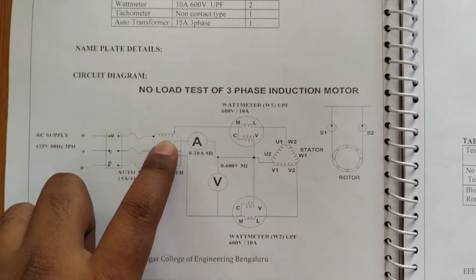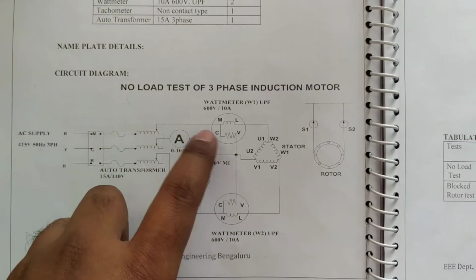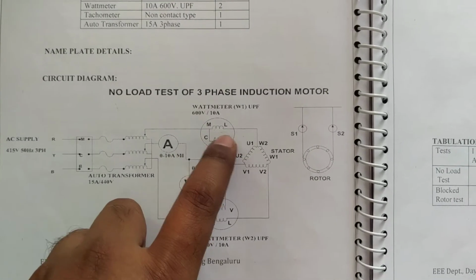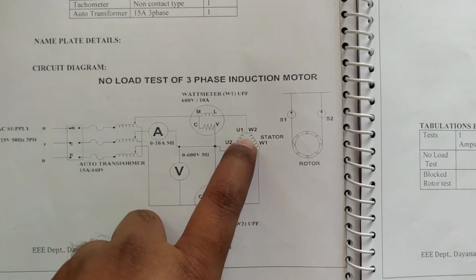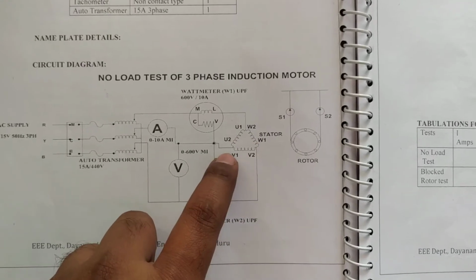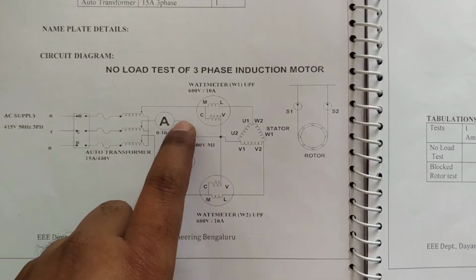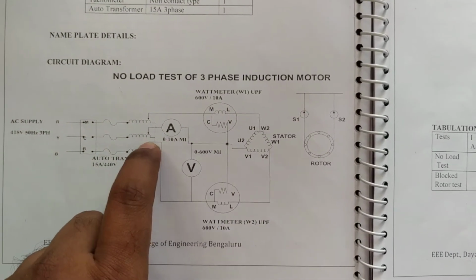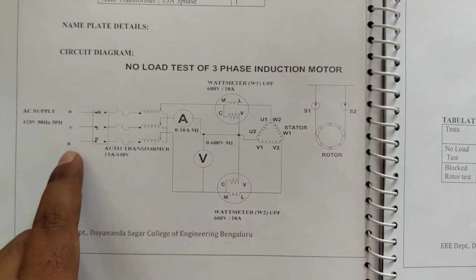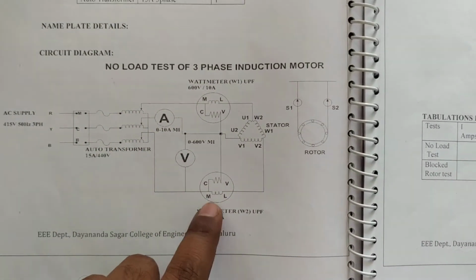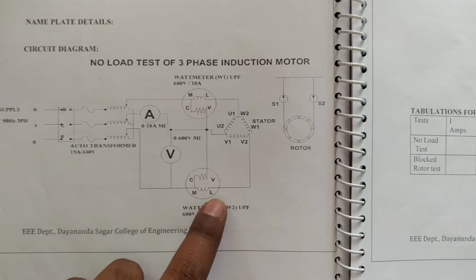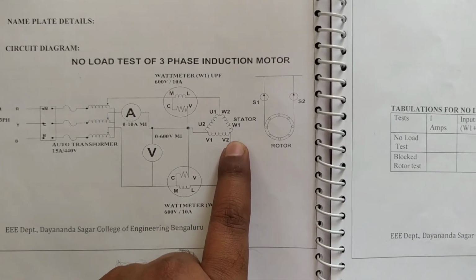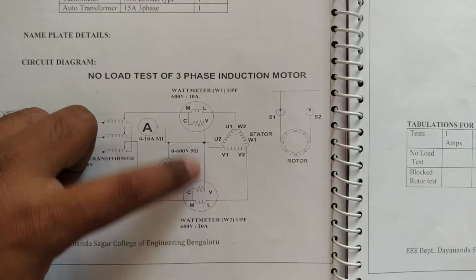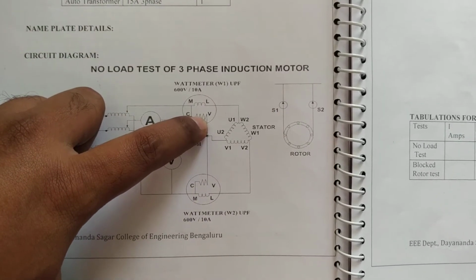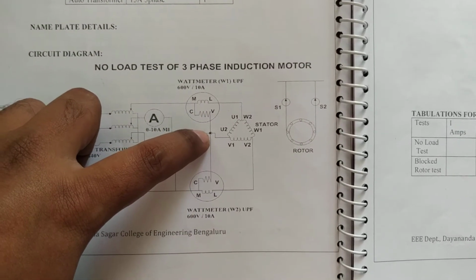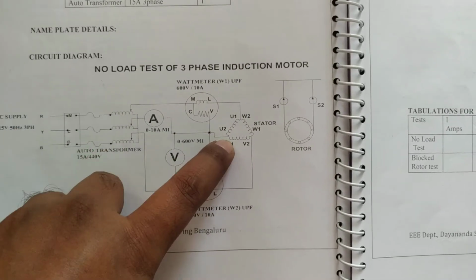Now first we will do the series connection. From the R phase it should be given to the M terminal of the wattmeter. Again, L should go to the first terminal of the stator. Again, the second terminal of the stator should come back to the Y phase through the ammeter. Again, the B phase should go to one more wattmeter M terminal. Again, L should go to the third terminal of the stator. Here we should take care that the V and V terminals of the 2 wattmeters should be shorted. Again, the one more terminal, that junction, should come back to the second terminal of the stator.